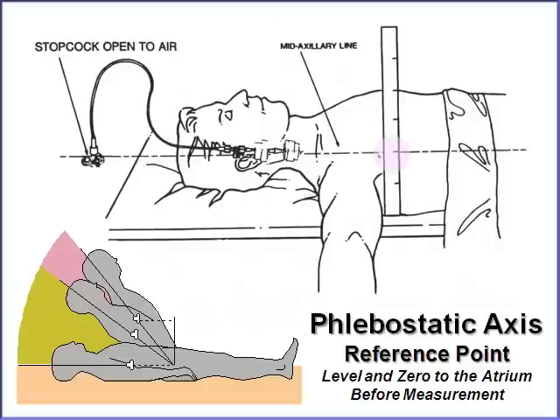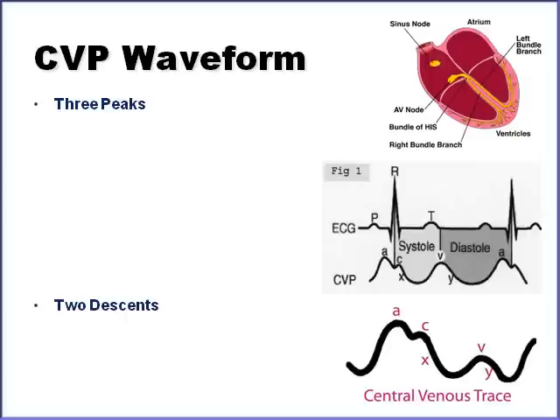Before we even tackle looking at the numbers on the monitor or interpreting the waveform, we need to make sure that the transducing system has been leveled and zeroed to the patient's right atrium — the phlebostatic axis. The phlebostatic axis is the point halfway between the patient's anterior and posterior chest at the fourth intercostal space. Then you line that up with the stopcock, the air-fluid interface, and zero it.